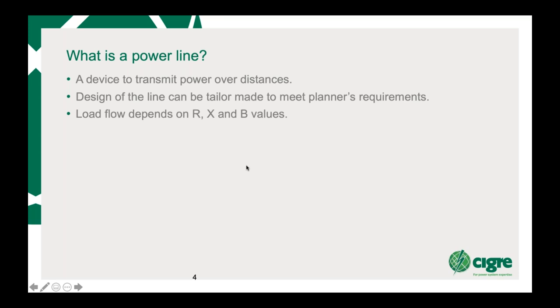So the first thing that you need to understand when you're looking at power line design is that a power line is not a group of conductors and towers. It is a single device which is used to transmit power over long distances. It's similar in a device to a transformer, although it is open to ambient conditions. And it's important to view a power line as a single device, because if you look at it as a section of towers, you tend to miss the interaction between the conductors, the towers, the phase spacings, and so on.